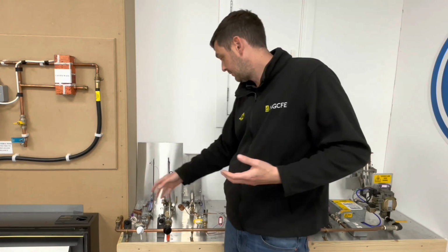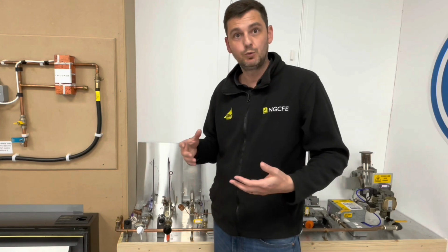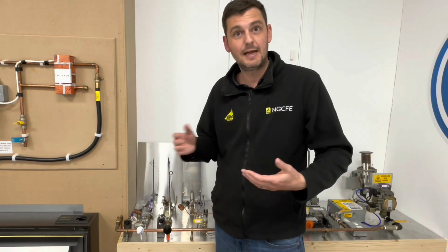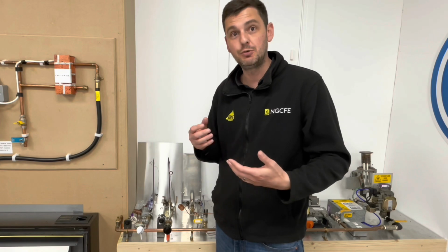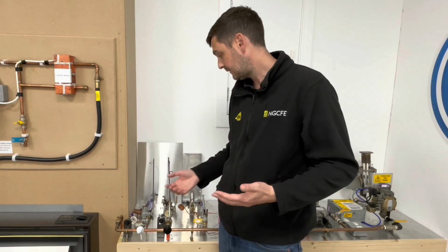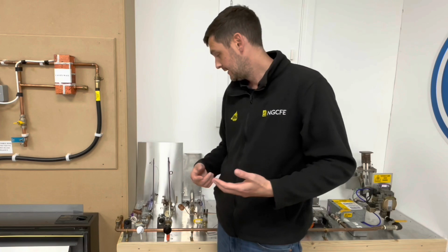Possible faults on the thermoelectric FSD side would be if you can't get the appliance to stay on, in which case there's an issue. The thermocouple might be broken, there might be a break in the circuit, it might not be making a connection properly with the magnet.